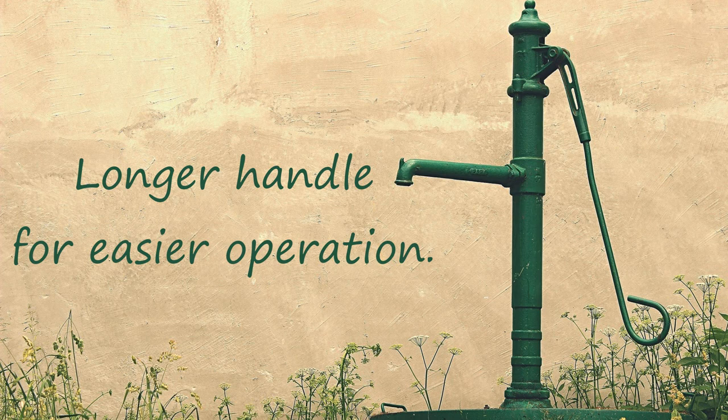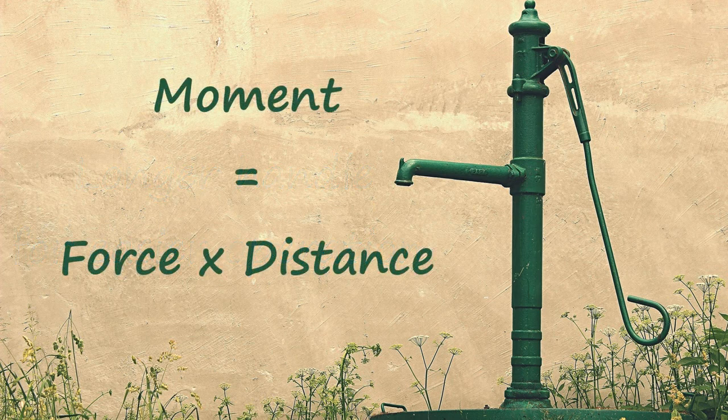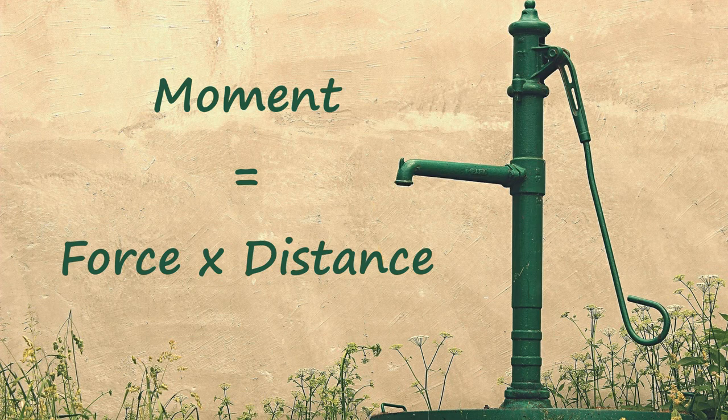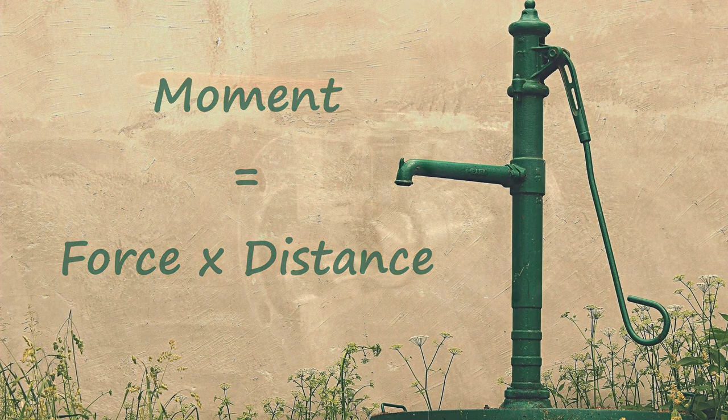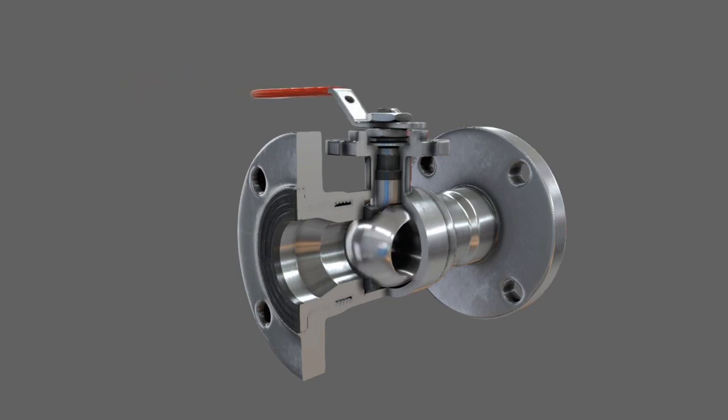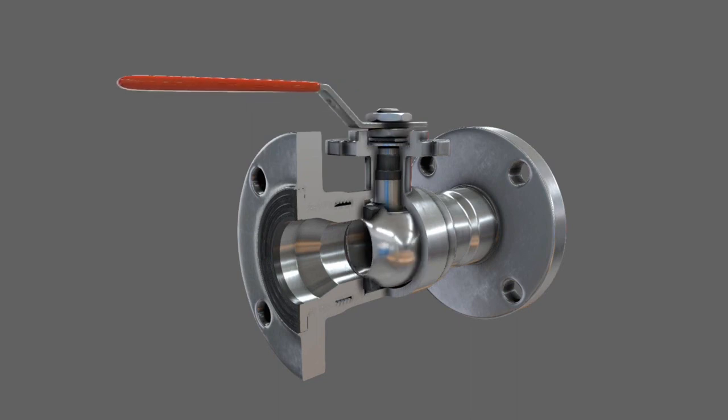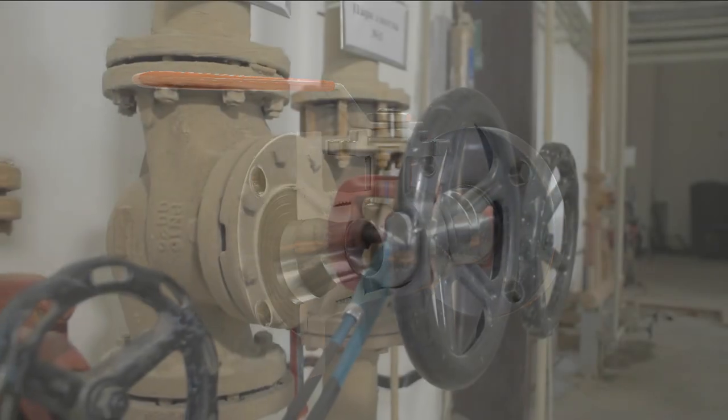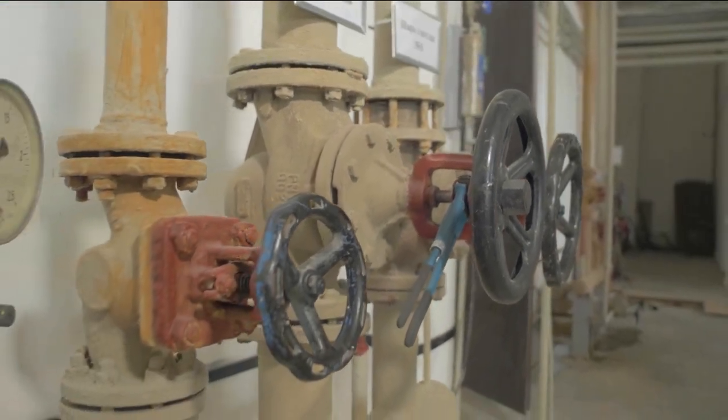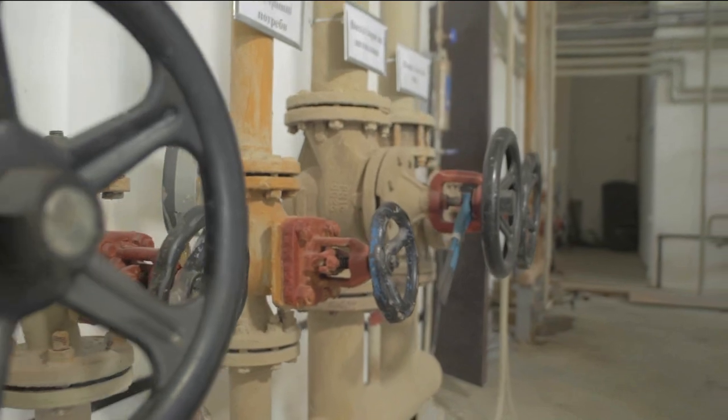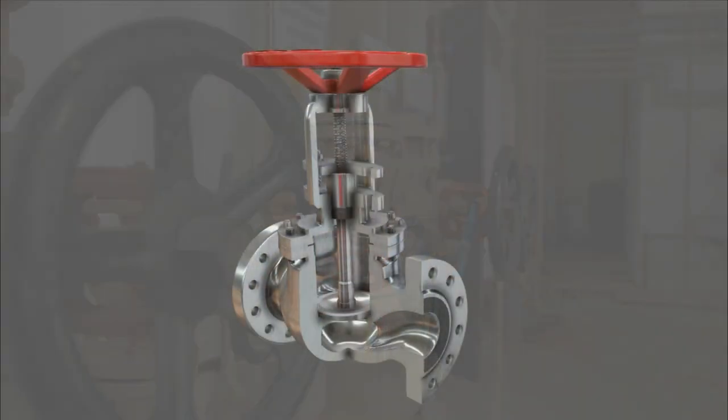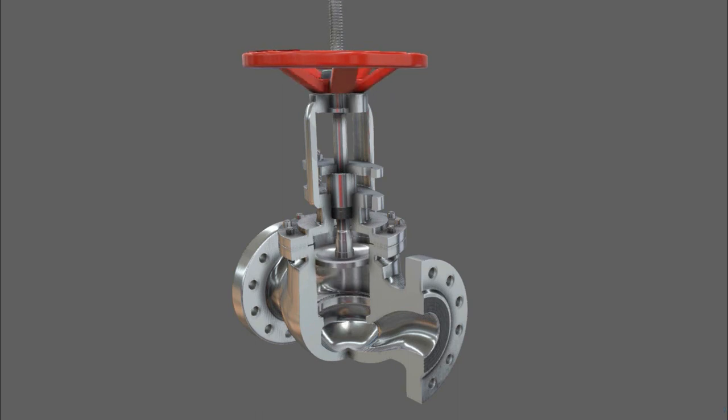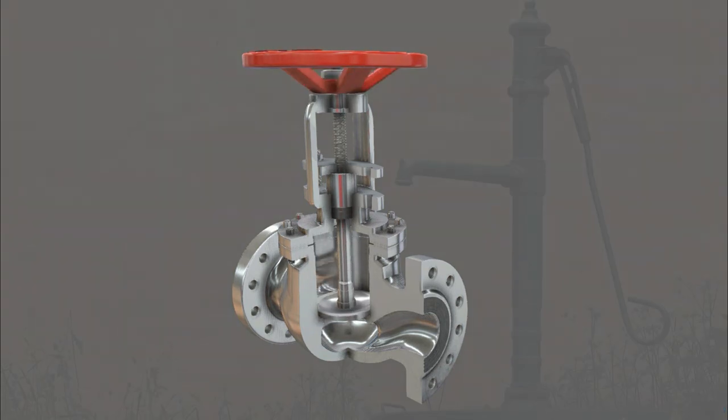Now this concept of M equals FD, or moment equals force times distance, is used all over the engineering world. We use it for many different parts, components, machines across all industries. If you look at a simple ball valve, the reason we have a handle on a ball valve is to make the ball valve easier to operate. If the handle is very short, it would be difficult to actuate or to open and close the ball valve. If we're looking at a globe valve, for example, they have handle wheels, but again, the handle wheel is designed so that we can apply a force a certain distance away from the pivot point. If the handle wheel is larger, then we can apply less force, but it will yield a larger moment.